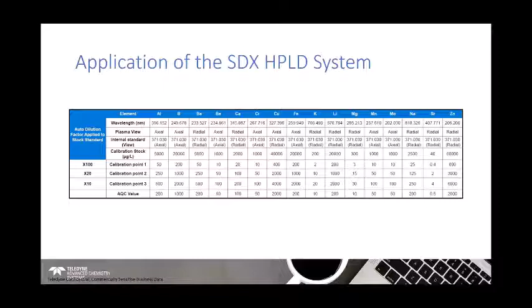Then there's an option for a prescriptive dilution. We can dilute a sample within a range of 2x up to 5000x. From here, we can generate our calibration standard solutions at different dilution factors from the same reagent tube, sample tube, and multi-element standard tube that's on the system. We can apply a blanket dilution factor to all of our samples. We can do what we like with our sample set. Then we have the last mode, which is a responsive dilution. If any of our samples fall outside of certain criteria, it can trigger a responsive dilution, where the ICP-OES system and the operating software calculate a more appropriate dilution factor that brings the sample within the calibration range, and I'll be talking more about that shortly.